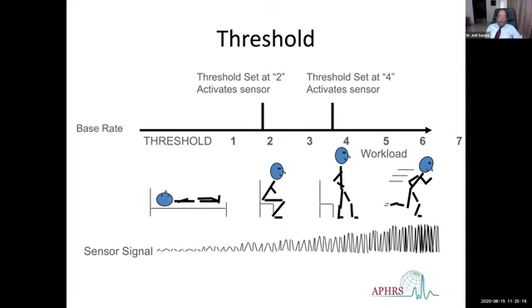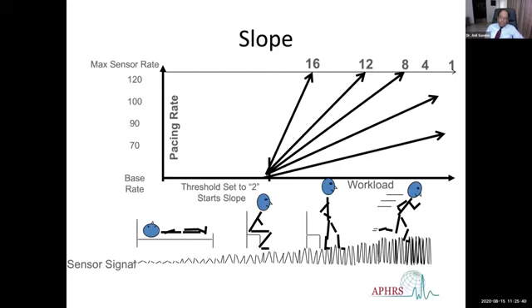Then the threshold is the activity level at which we want the rate response to kick in. So we may want a low activity, medium activity, or high activity when we want the sensor response to kick in. Then it can be made very aggressive or more muted. In our patient that we discussed in the beginning, the response is very muted. So we can select a better slope so that the response is more aggressive. For the same level of activity, we can have a muted response, or we can have a more aggressive response. So that's how we program it.